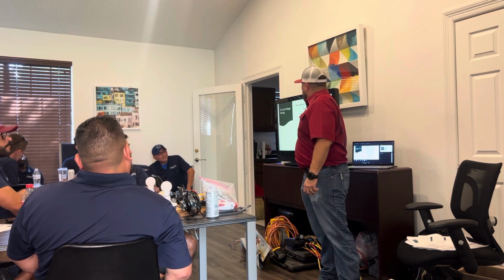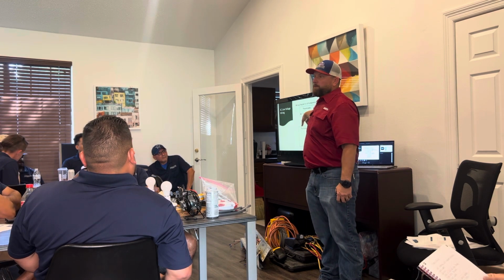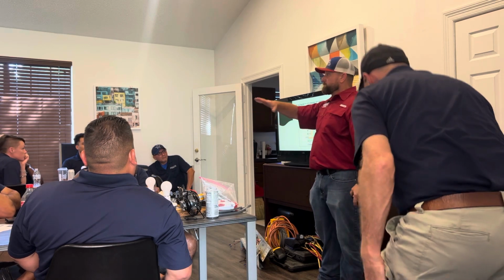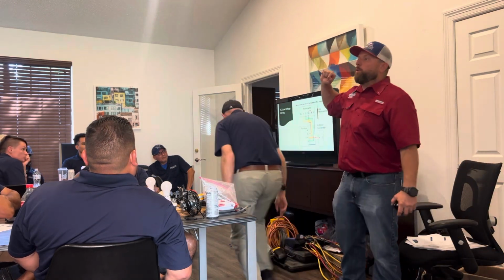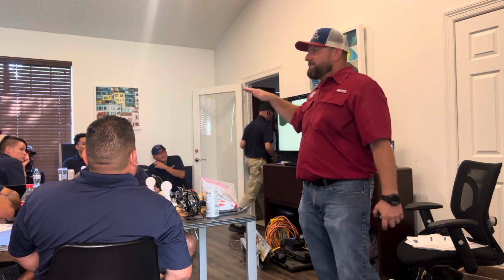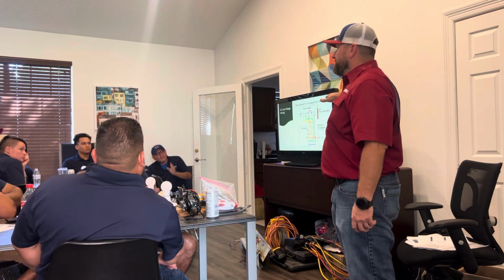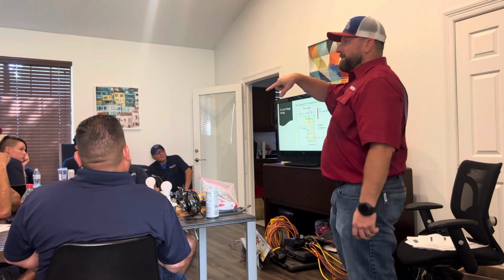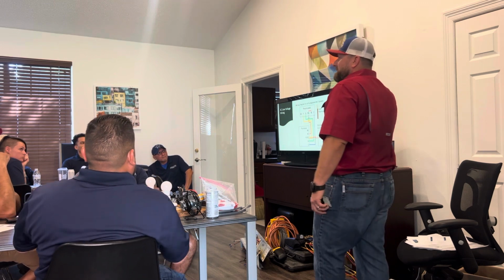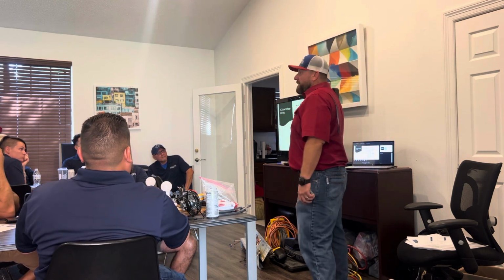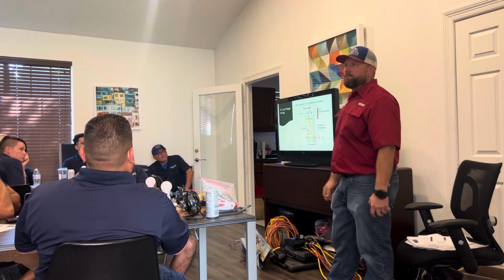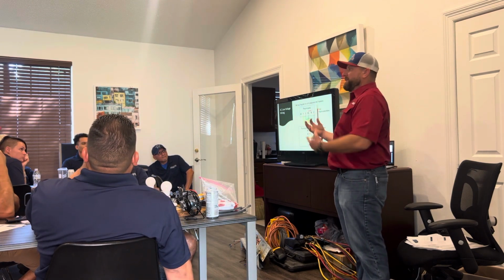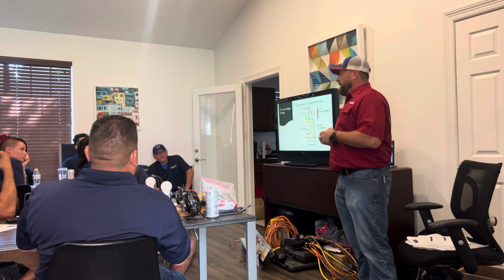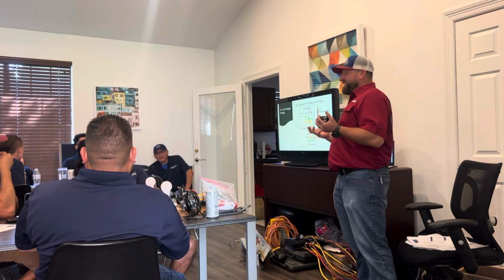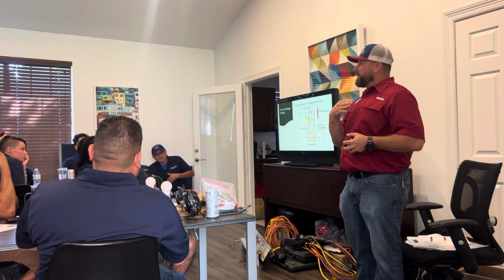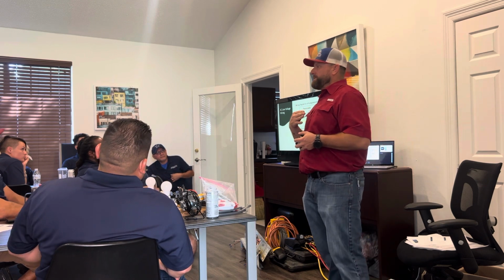So at the thermostat, you won't have this in most of y'all's properties. And so if that's the case, how does that thermostat get powered up? Batteries. So if you see a blank screen on there, you already know there's no common there, we need to check batteries. Most of the time you pull it off, you'll see it's corroded and built up. If you have one corroded, you're laughing, you've seen that. If you have one corroded and built up, replace the whole thermostat. Don't jack around with it, you're gonna waste your time.